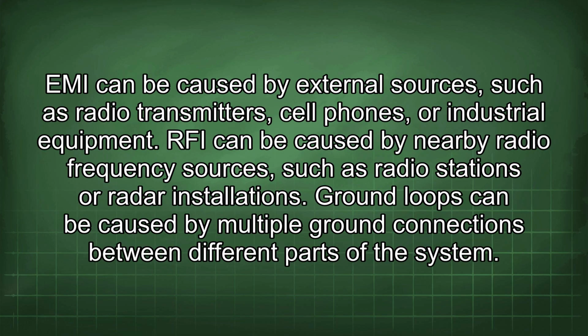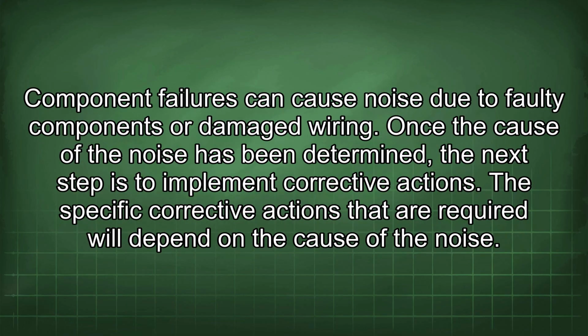EMI can be caused by external sources, such as radio transmitters, cell phones, or industrial equipment. RFI can be caused by nearby radio frequency sources, such as radio stations or radar installations. Ground loops can be caused by multiple ground connections between different parts of the system. Component failures can cause noise due to faulty components or damaged wiring. Once the cause of the noise has been determined, the next step is to implement corrective actions.